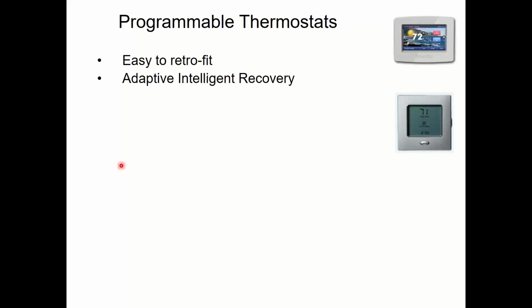So if your building's going to go occupied at 8 a.m., instead of saying, well, let's put the schedule at 6 a.m., that way we know we're covered, you put 8 a.m. in there and let the thermostat figure out what time it needs to start to get the building warm enough or cool enough by 8 a.m. And then it might start at 7:53 because it's a super mild day out and 7 minutes is all it needs. Or it might start at 6:47 because it needs an hour and 13 minutes to get there because it's a cold day out or whatever.